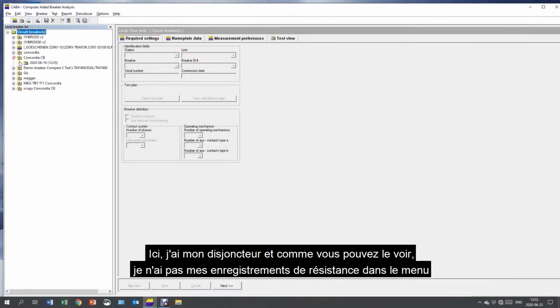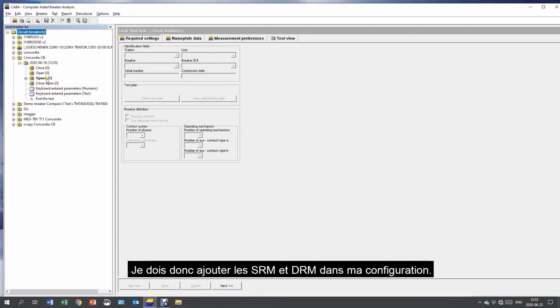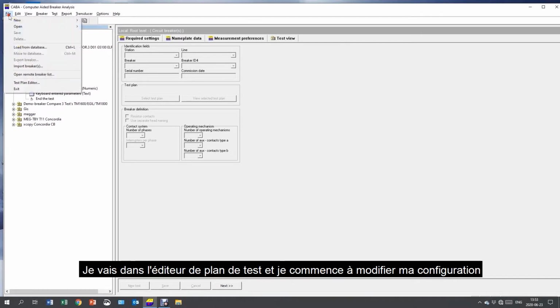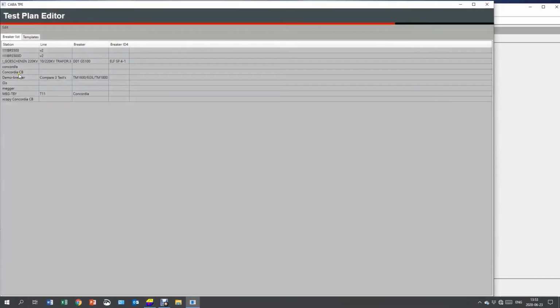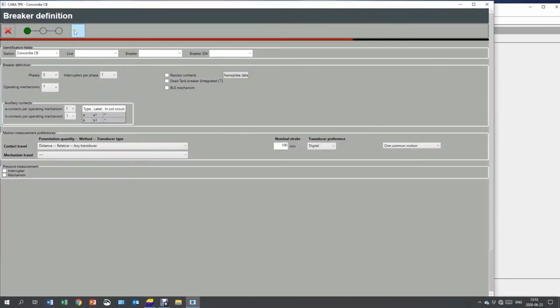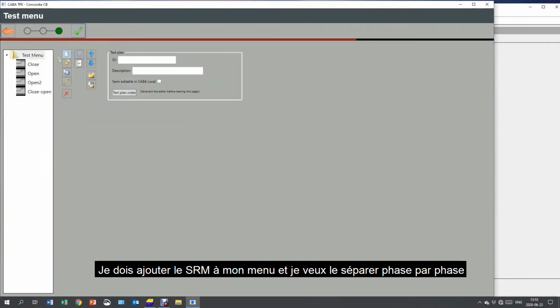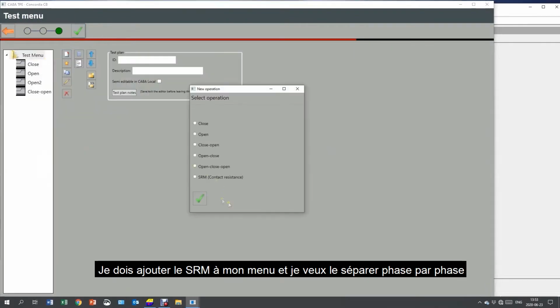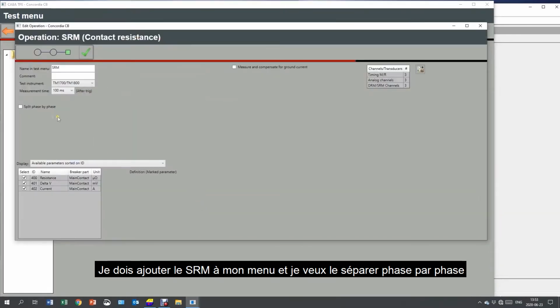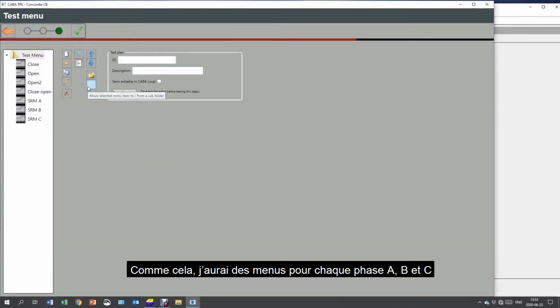Here I have my circuit breaker, and as you can see, I don't have my resistance recordings in the menu. So I need to add SRM and DRM in my setup. I go to the test plan editor and I start changing my setup. I need to add the SRM to my menu, and I want to split it phase by phase. By that, I will now have menus for each phase, A, B, and C.